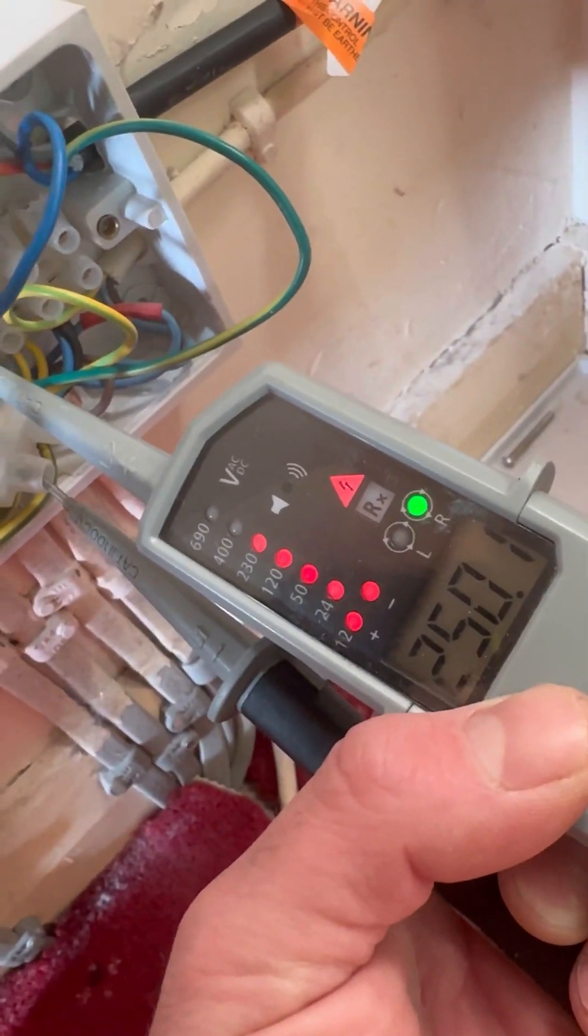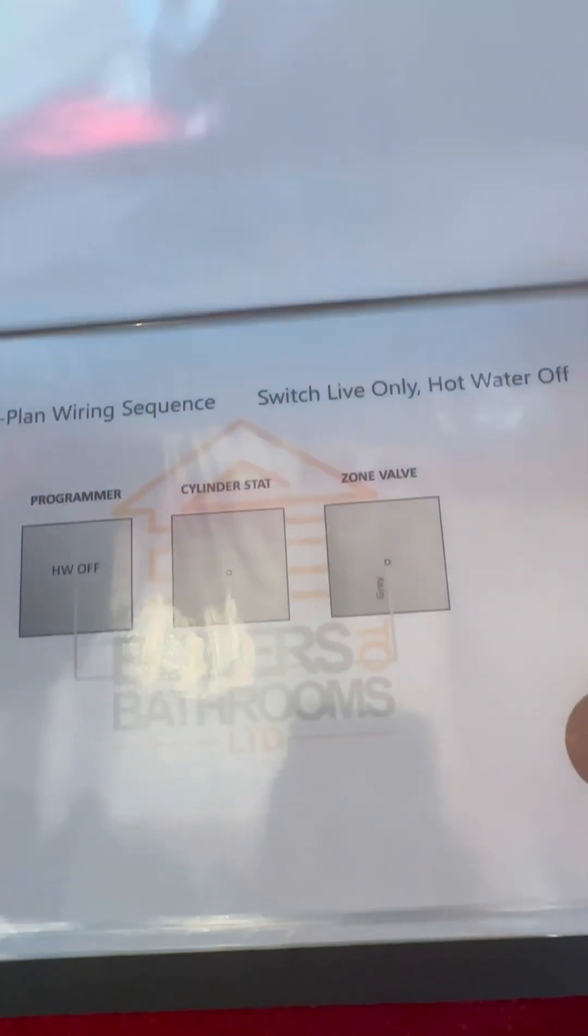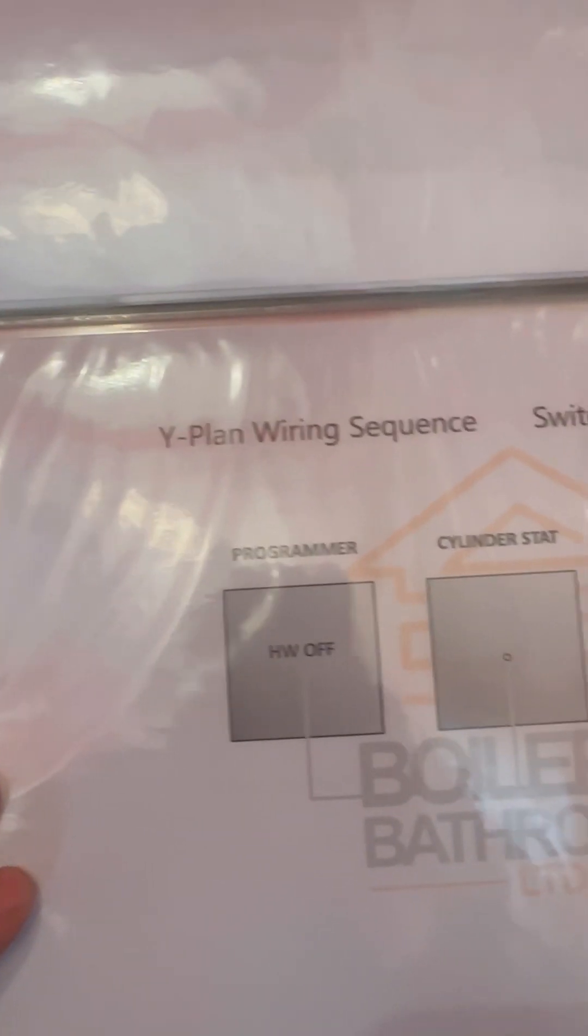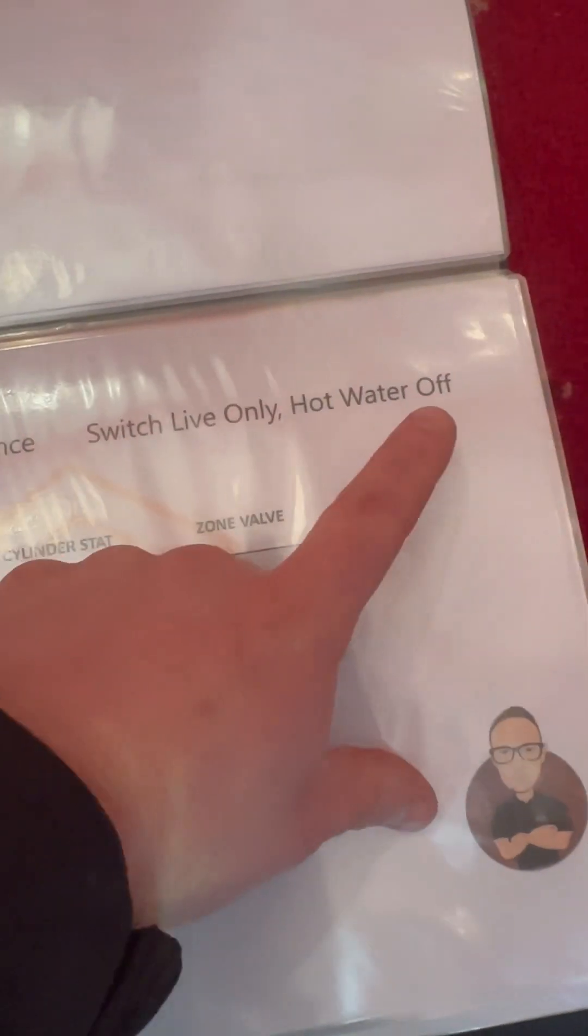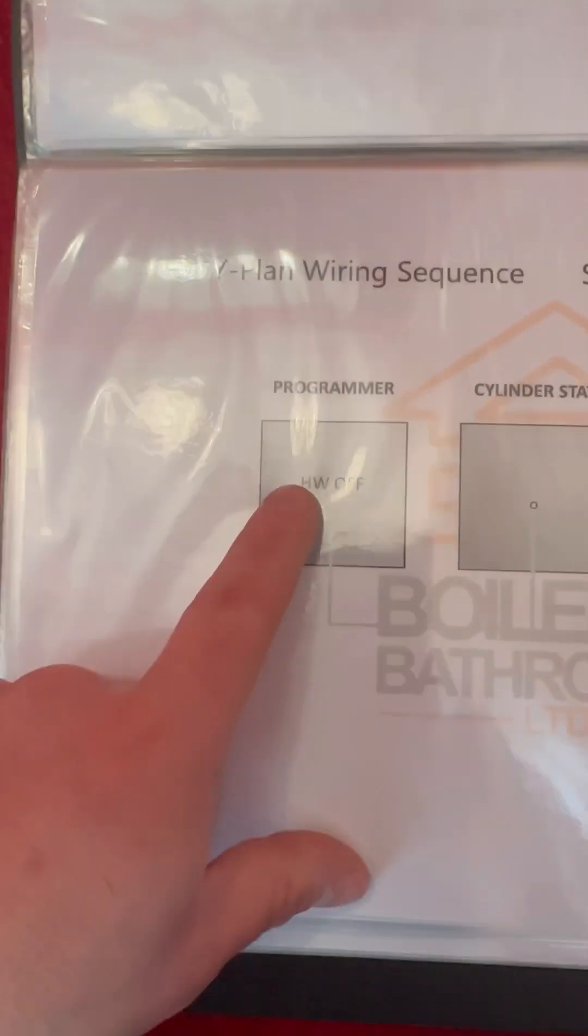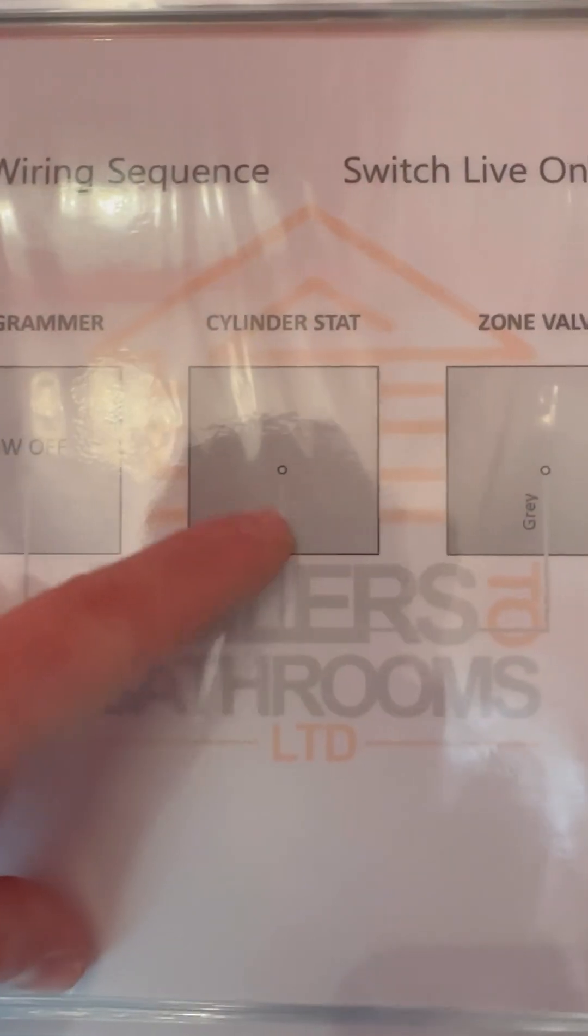But we'll get 240 on orange. And then we'll do switch live hot water off. So this will also check to make sure the programmer's doing its job properly because it should send 240 up to gray.